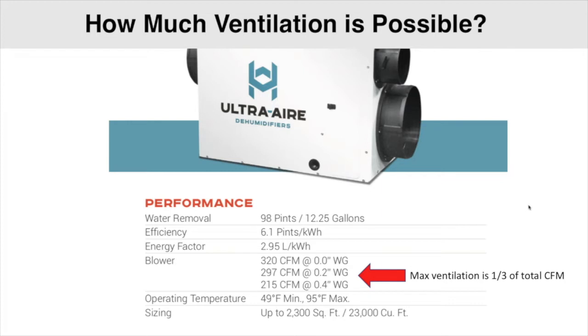Now, we do have the dedicated duct for ventilation on all of our dehumidifiers, except for the Ultra Aire 70 pint, because the footprint of the unit is so small, so you have to tie in to the return of the dehumidifier. And then our in-wall dehumidifier does not provide any ventilation. The duct has a damper in it that you can adjust to set your ventilation. Obviously, you're going to have to test it to make sure that you're bringing in what you need. But again, the max that you can get is about 1/3 of the total CFM of the unit.